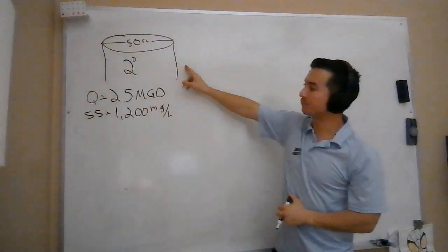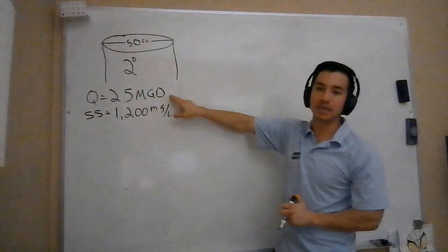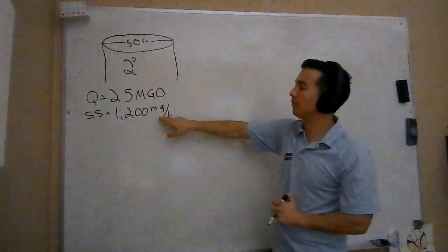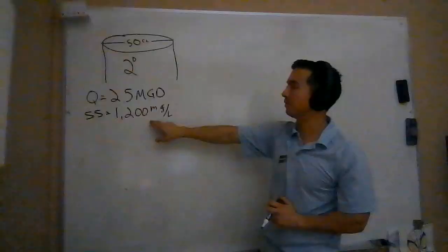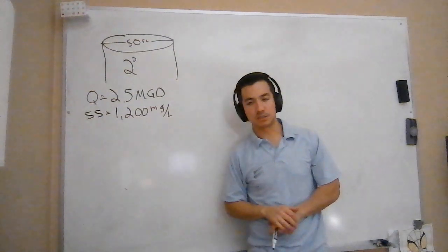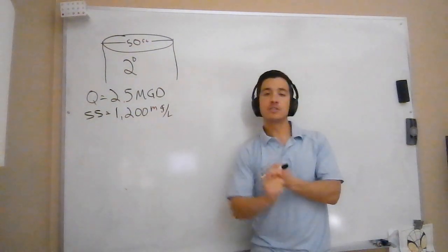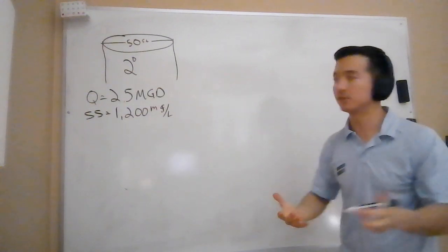So here's our secondary clarifier. It's got a 50-foot diameter, treating a flow of 2.5 million gallons per day (MGD), and we measure a suspended solids concentration of about 1200 milligrams per liter. We're going to be calculating two things here: the weir overflow rate and the solids loading rate. We'll start with the solids loading rate because we want to settle the solids out first.